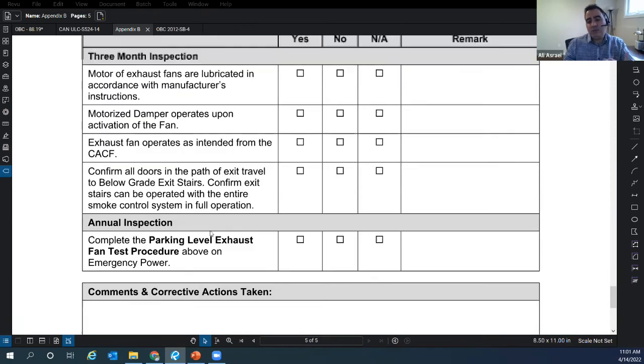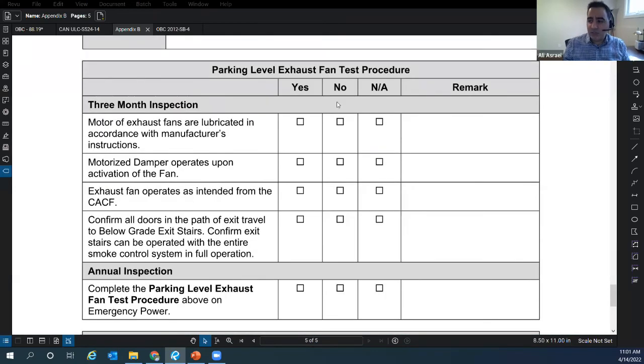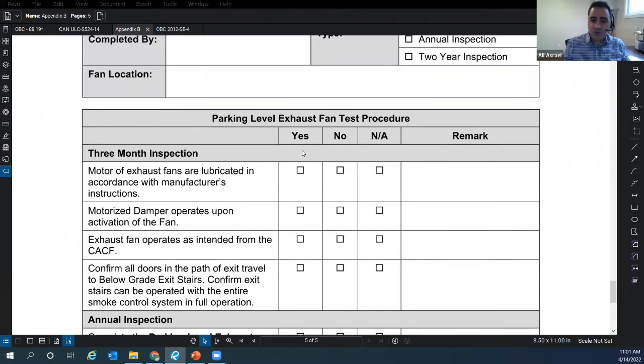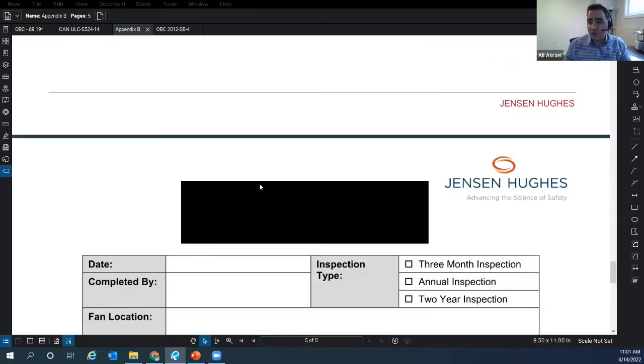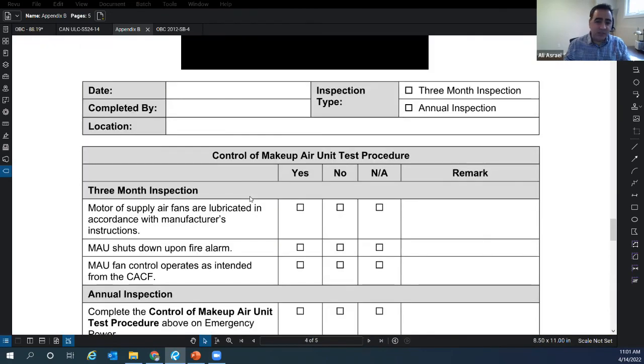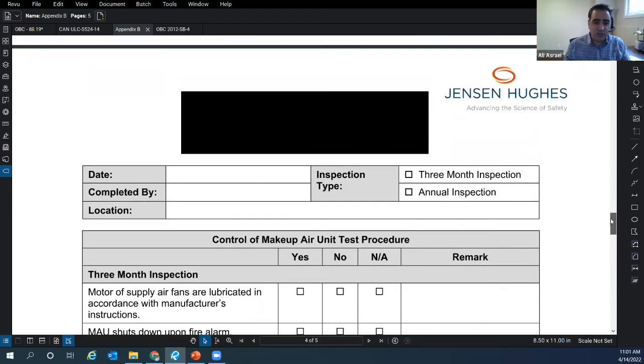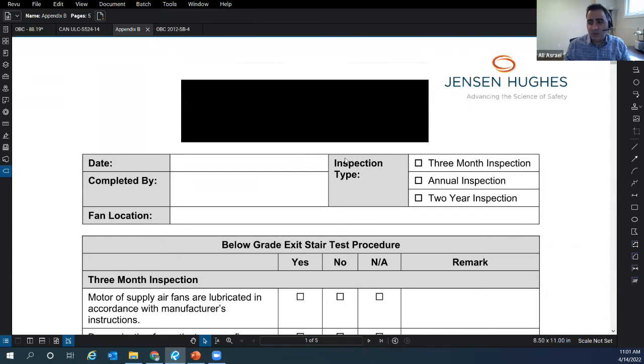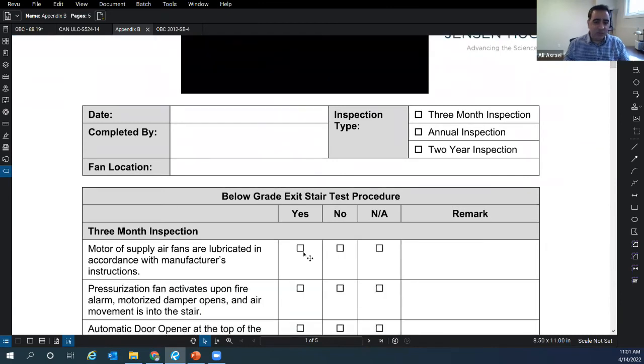This is the tables again, but as part of this report, you should first see an assessment. The report is talking about the entire building: what measures they used, the size of the fans, and the specification of the things in the building. And you see the results, like a result similar to this, unless they confirm that we reviewed the air balancing and skipped basically the initial test. Otherwise, you have to see something like this with the test results.